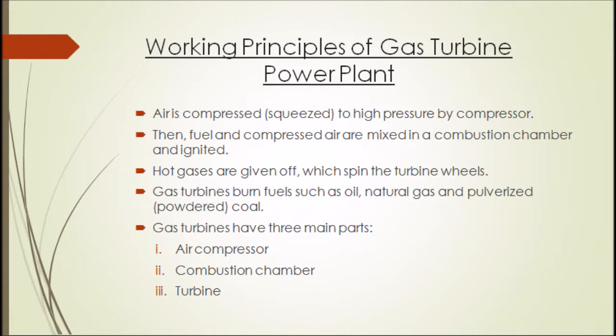The combustion produces a high-temperature, high-pressure gas stream that enters and expands through the turbine section. The turbine is an intricate array of alternate stationary and rotating aerofoil section blades. As hot combustion gas expands through the turbine, it spins the rotating blades. The rotating blades perform a dual function: they drive the compressor to draw more pressurized air into the combustion section and spin a generator to produce electricity.